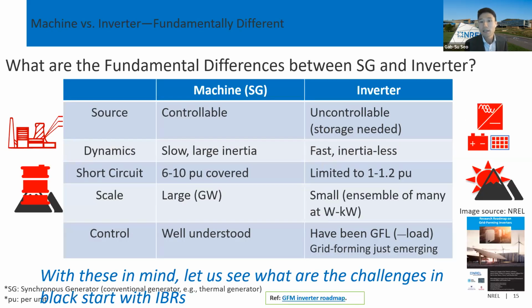This slide gives the audience some background to understand the fundamental differences between machines and inverters, which are very different in many aspects. First, inverter-based resources, or IBRs, are not fully controllable in terms of prime power source. For example, solar power is not available in the middle of the night. And since inverters are electronics, their dynamics are much faster than a machine's. Inverters do not have large inertia, simply because they lack rotating mass, unlike existing synchronous machines. That inertia serves important roles, such as slowing down frequency variations, so it's a big factor.